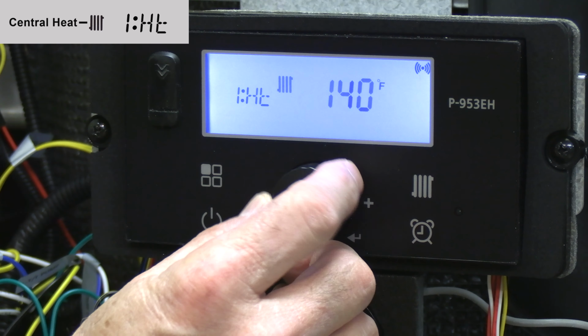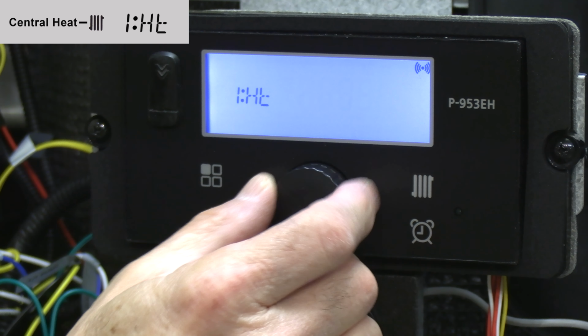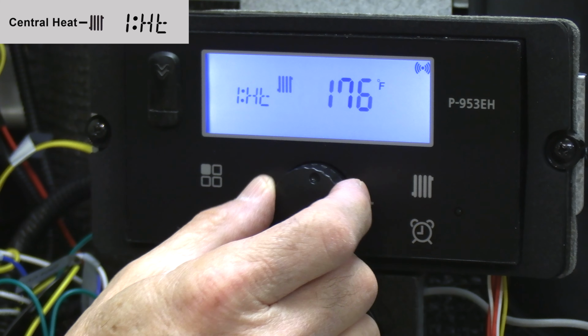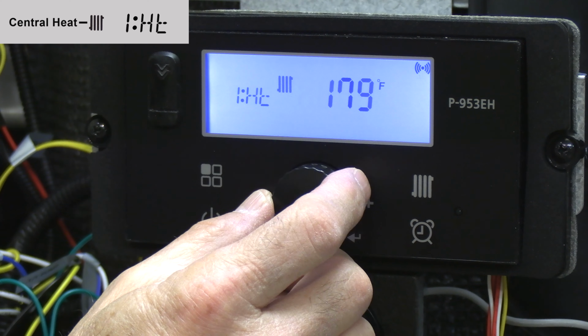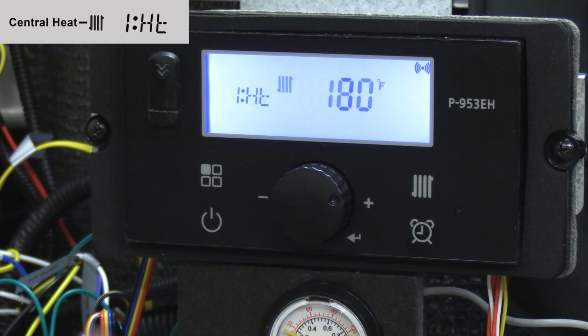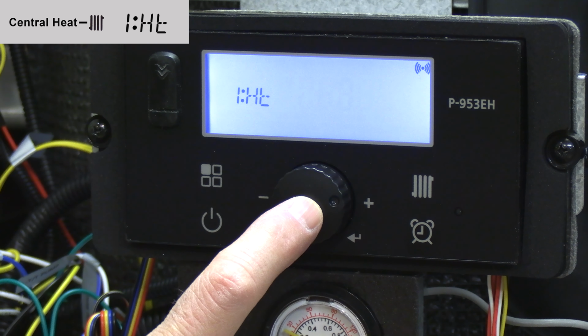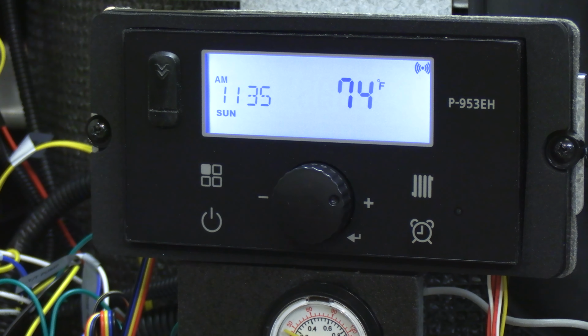So what type of convectors do you have? An example, if it's a high temp system, I'll need 180. So I will adjust this up in that example to 180. Or maybe it's an in-floor radiant and the max temperature I want is 130 on a 0-degree day. So adjust your temperature to what you need, and to store that, very simply, press the select button again. We've now stored, in this example, a 180 degree set point.